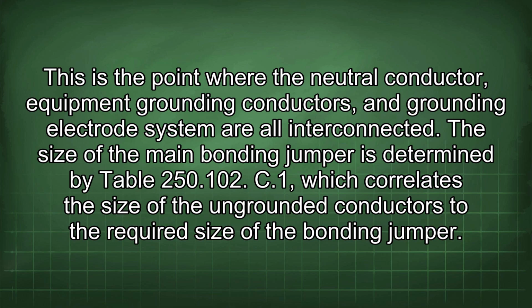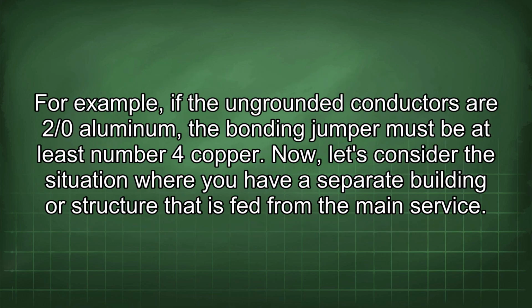The size of the main bonding jumper is determined by Table 250.102 C1, which correlates the size of the ungrounded conductors to the required size of the bonding jumper. For example, if the ungrounded conductors are 2/0 aluminum, the bonding jumper must be at least number 4 copper.